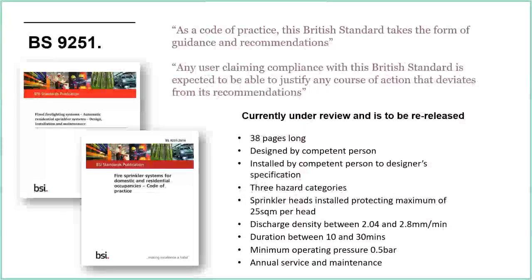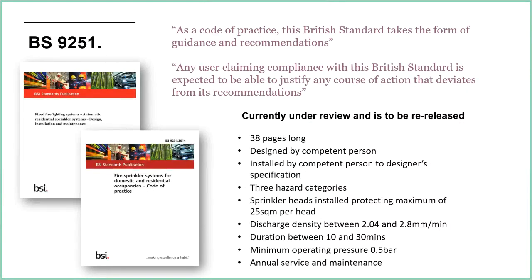BS9251 is 38 pages long. A few highlights: designed and installed by a competent person to a designer specification. There are three hazard categories — one, two, and three. The more complex the building, the more occupants, the kind of people living there, and building height would all feed into the hazard category assigned to that particular building. Sprinkler heads are installed protecting a maximum of 25 square meters per head.